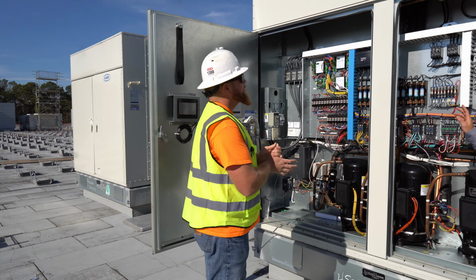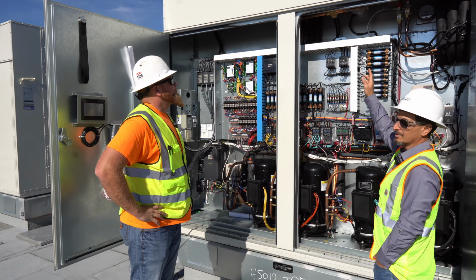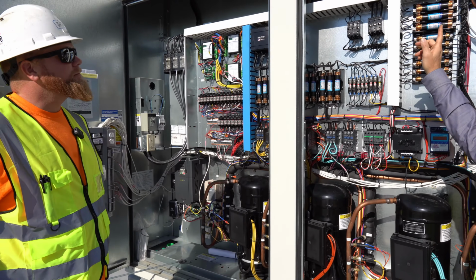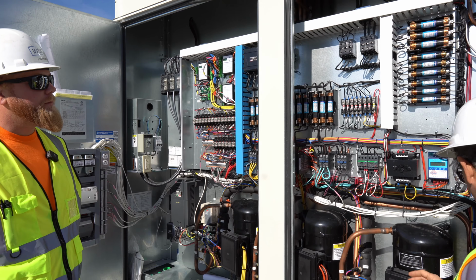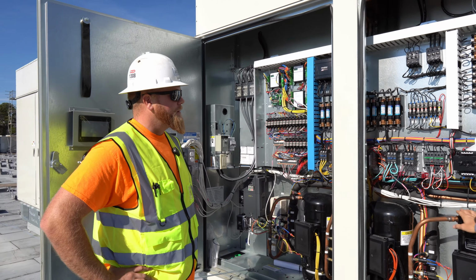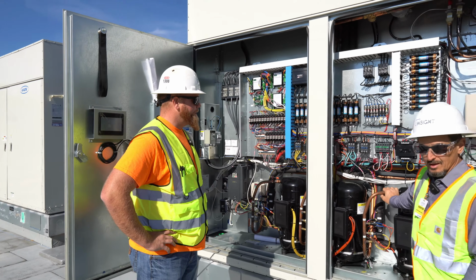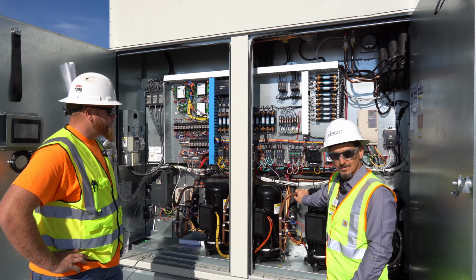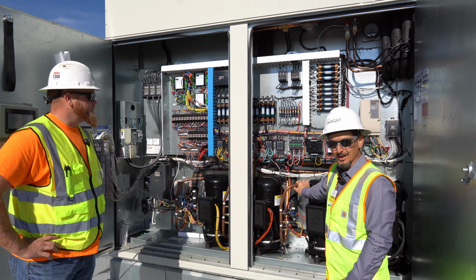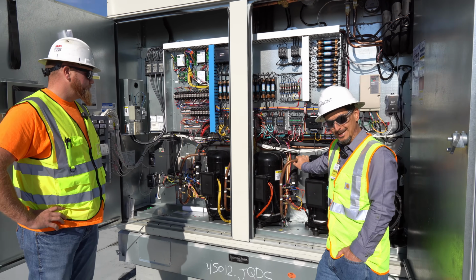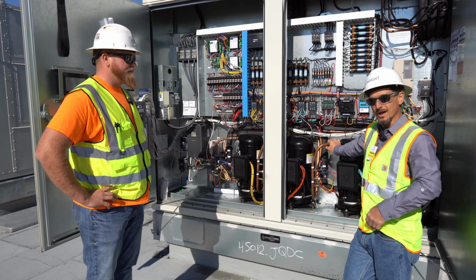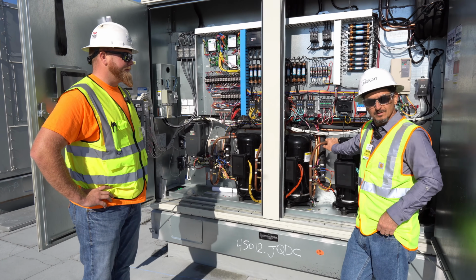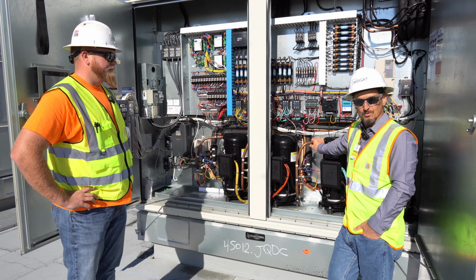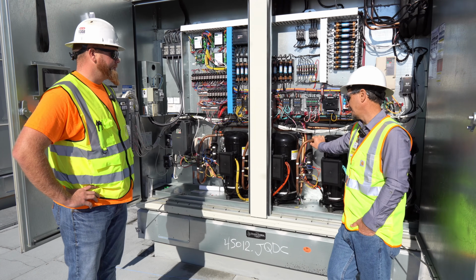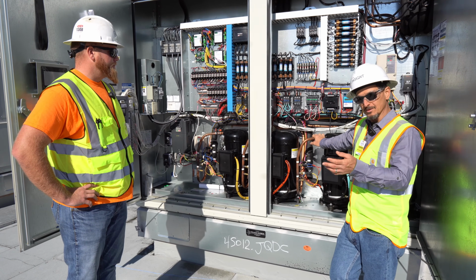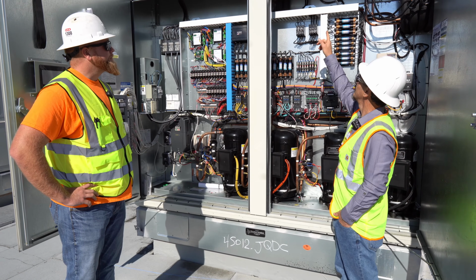So one of the things to point out is we talked about hot gas reheat. These are the 3-way hot gas reheat valves. We get a lot of questions on that, so I'll just go over that real quick. The discharge of the compressor would normally reject the heat to the atmosphere if you had a condenser coil on here. In this case, it would normally reject the heat to the coaxial water-cooled condenser, which is ground source water supplied. And that's what we do here, but when we need the reheat, it diverts the 3-way valve.